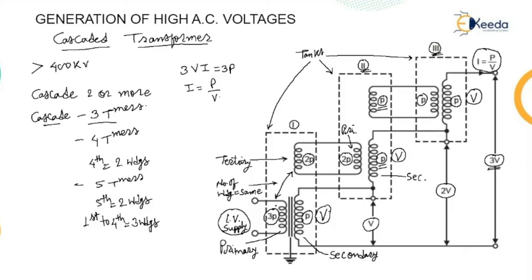This is all about the cascaded transformer for the generation of high AC voltage. The difference from a step-up potential transformer is that in a potential transformer there are only two windings — primary and secondary. In a cascaded transformer, N-1 stages must have three windings and the Nth stage should have only two windings. The power loading on lower stages becomes higher, but the current passing through each secondary winding in each stage will be the same, equal to I equal to P divided by V. Thank you.